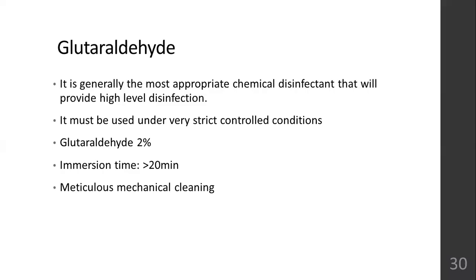Glutaraldehyde, it is one of the most appropriate form of chemical disinfectant that can provide high level of disinfection. And under very strict controlled condition, glutaraldehyde is used. Glutaraldehyde 2% is used. Okay. At least more than 20 minutes is the immersion time. Whatever instrument you are using to disinfect, okay, more than 20 minutes, it has to be in contact with glutaraldehyde. And before that, meticulous mechanical cleaning, that is manual cleaning, has to be done. Without cleaning, do not dump the instruments in glutaraldehyde solution. Cleaning has to be done. Okay.